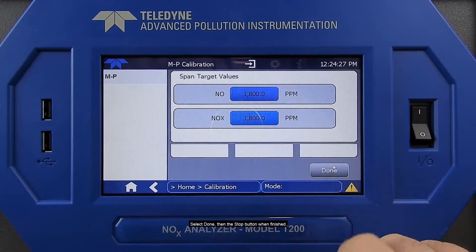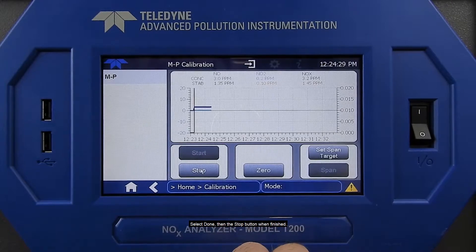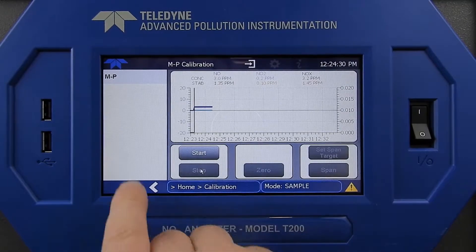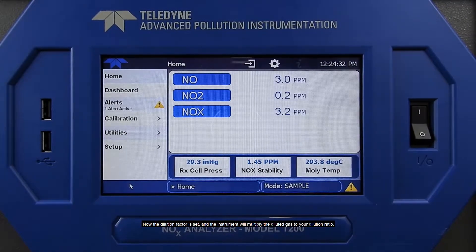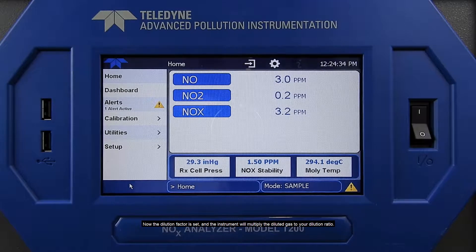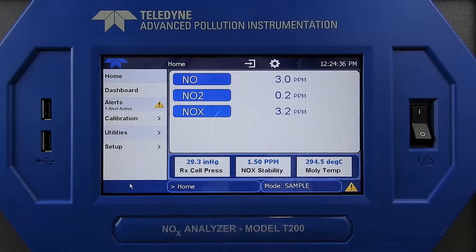Select Done, then the Stop button when finished. Now the dilution factor is set and the instrument will multiply the diluted gas to your dilution ratio.